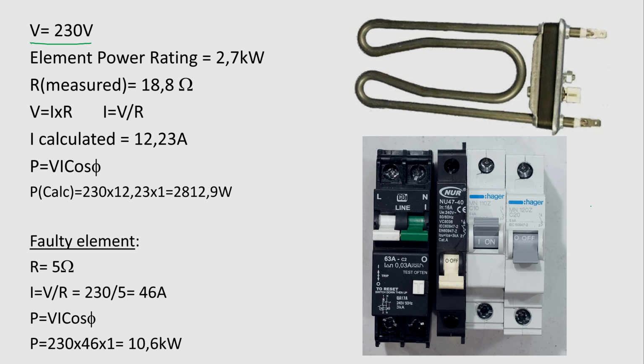Right, now just analyzing some of the electrical values, the element which I showed in the video is a 230 volt element, and it was marked as 2.7 kilowatts. Now I measured the resistance and it came to 18.8 ohms. That means I was measuring the resistance between the element terminals, so it should be a lowish resistance. Now if I calculate what the current would be, in this case it would be 12.23 amps.